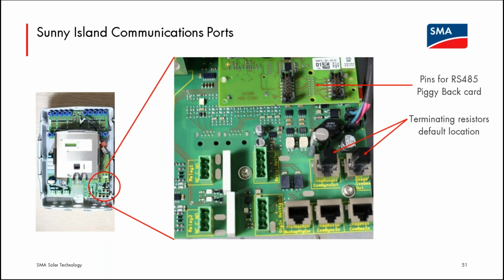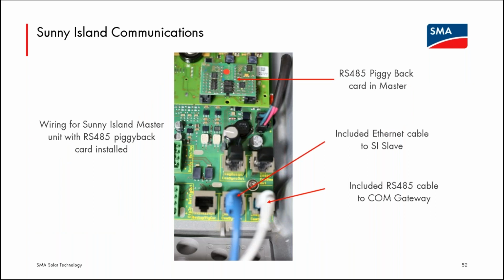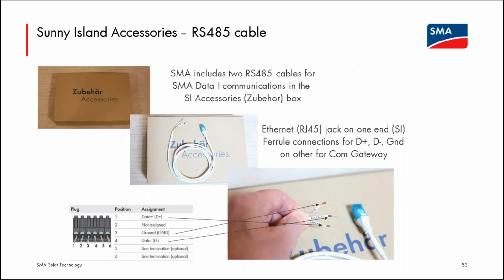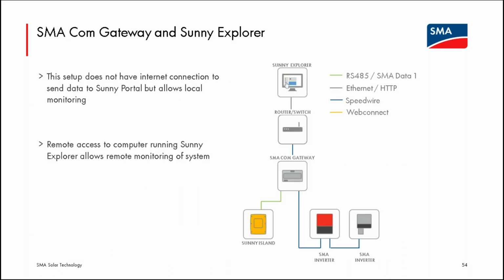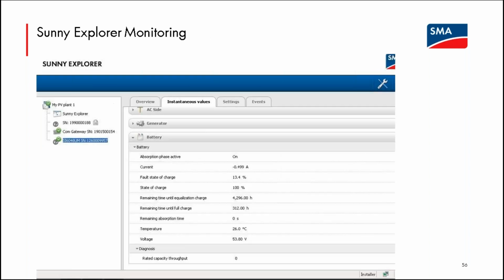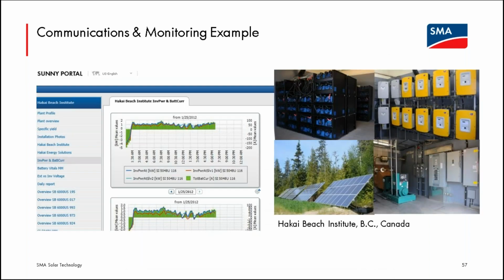So if you have several Sunny Islands and you're monitoring them with the COM gateway, only the master device needs the RS-485 piggyback. And then the rest is wiring between Sunny Island devices and then off to the COM gateway. These are some pictures we'll provide in this presentation in the accessories bag to do that RS-485 wiring between the master Sunny Island and the COM gateway. And again, that can be done locally. And this is a screenshot of Sunny Explorer showing local monitoring.